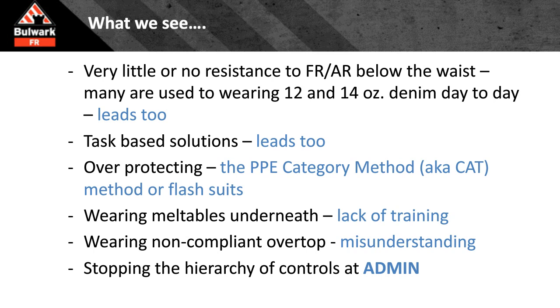I say that and everyone flinches on the webinar because, of course, we don't. But where do we see that? Combustible dust hazards. Why? Most combustible dust webinars and training walk all the way down to housekeeping and don't address PPE. A combustible dust hazard is a chain reaction flash fire. In fact, if you read the combustible dust standards, they reference NFPA 2112 compliant garments as your PPE for that hazard. So your last line of defense is PPE, not admin controls.